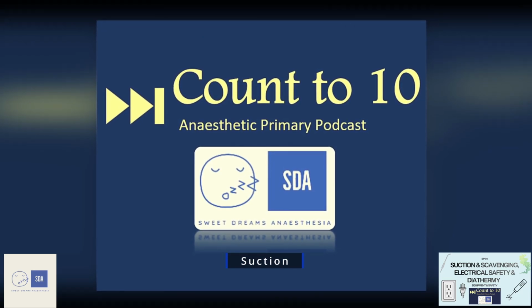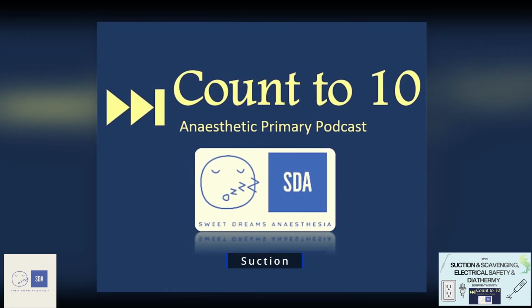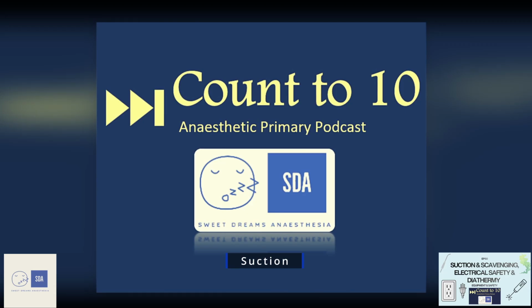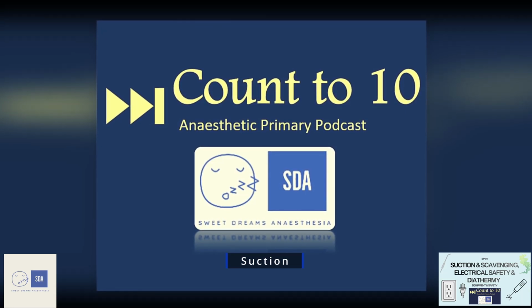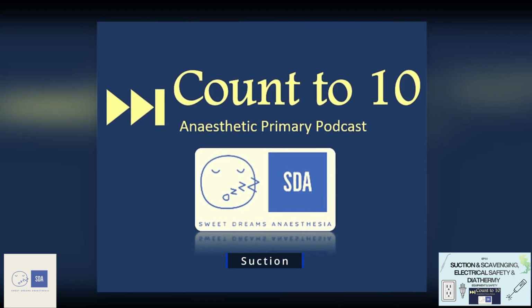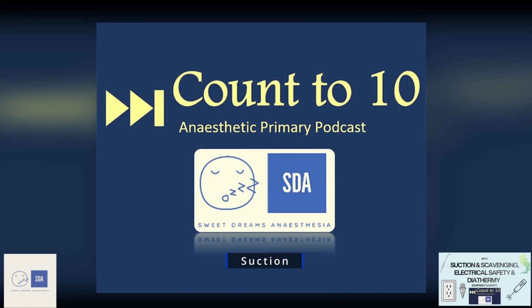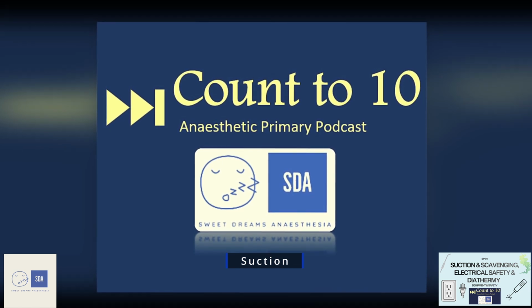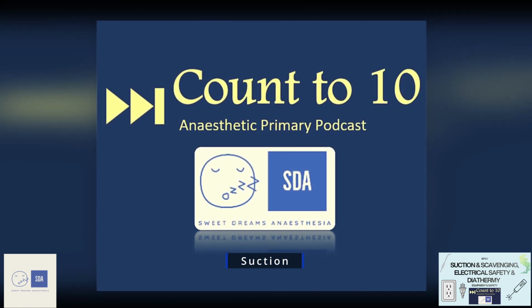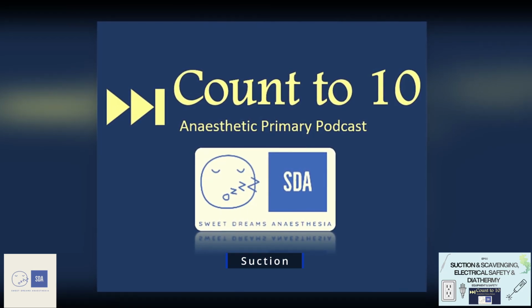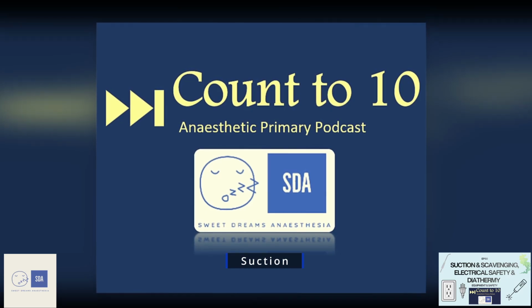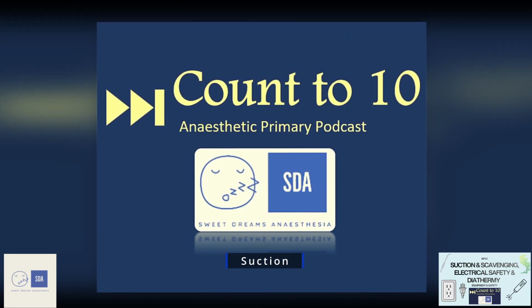We can utilize these physics principles by using things like air and pushing air through a narrow constriction, which then creates a negative pressure, and that negative pressure again can be used as a source of your suction. This, however, is not commonly done, especially in a big hospital, because it's just going to waste a lot of gas. But when you're in a rural setting and you might not have a central facility vacuum, you might use this as your main source of vacuum. And for this, you then need an air cylinder to ensure it works appropriately.